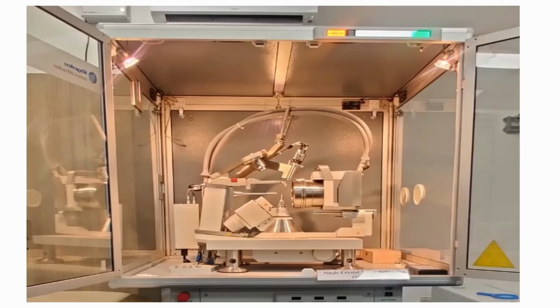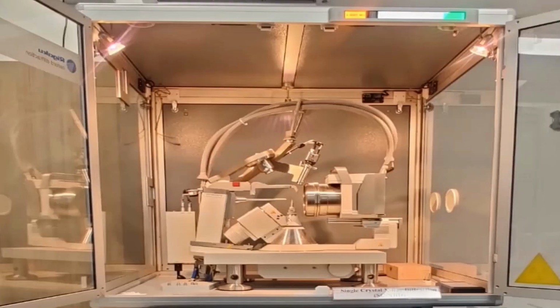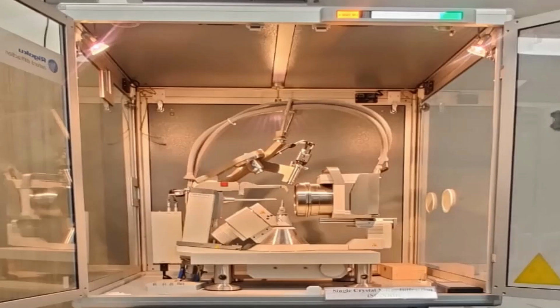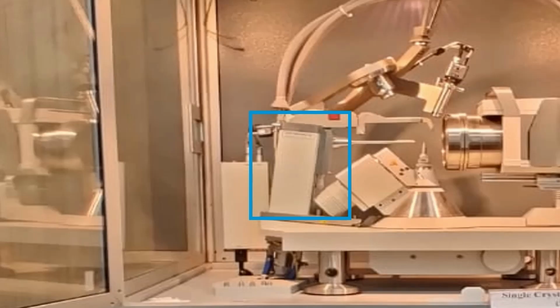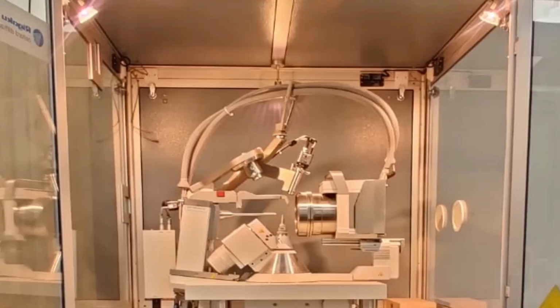This is the single crystal XRD from Rigaku, which is from Japan, and the model is Excalibur Gemini. So as we can see here, the diffractometer and CCD detector are mounted inside the cabinet. Let me quickly introduce the parts that are located inside the single crystal XRD. This is our X-ray tube, which is mounted on the goniometer, and it is powered by high voltage X-ray generators. This is our collimator. The target metal is molybdenum here.